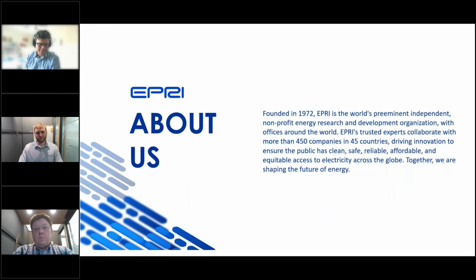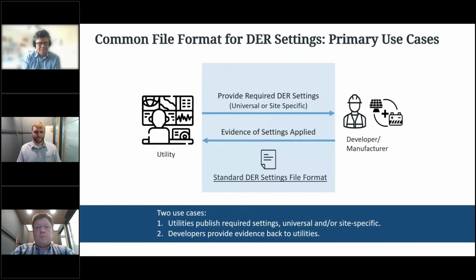What we're talking about today is the common file format for DER settings exchange. A very simple, but very powerful idea. We're not really talking about what the settings should be, since we already know what the settings are: the IEEE 1547 standard has set out a list of DER settings or functions that you need to configure and be certified for, by IEEE 1547 or nationally recognized test labs like UL or others.